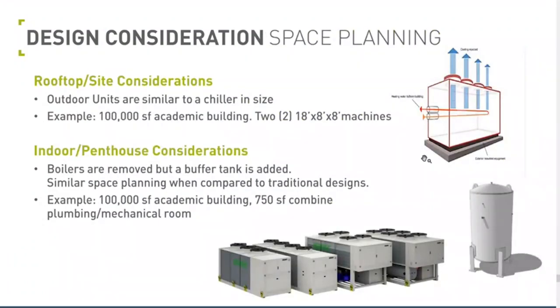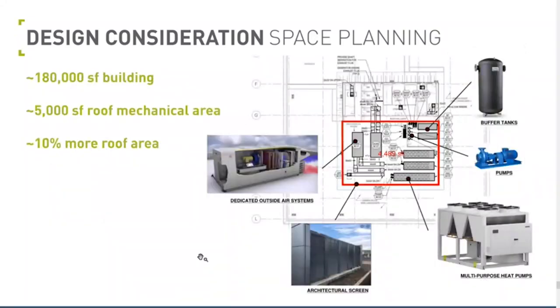The size of this equipment is a lot bigger than our traditional natural gas boilers that we just lay out somewhere, right? Takes up a lot more space. It requires a ton of airflow. You can't just lock it in a closet somewhere. You need a good amount of airflow for this to be able to extract that heat we talked about. So they're similar size to a chiller. And they're big machines and they're expensive machines. I think I have another slide on cost. They're big and expensive, and they require some other bits and pieces that take up space and cost money, right? Some buffer tanks, they require different type, sometimes additional things within the infrastructure and distribution to account for that. So it's something to be aware of.